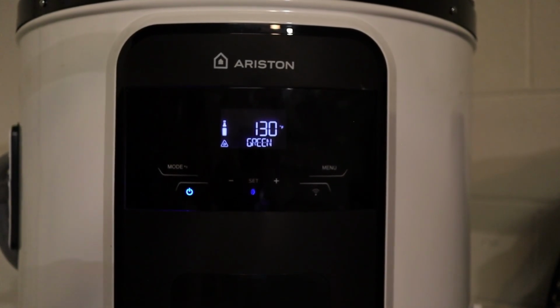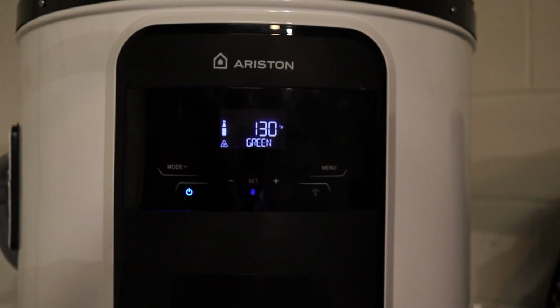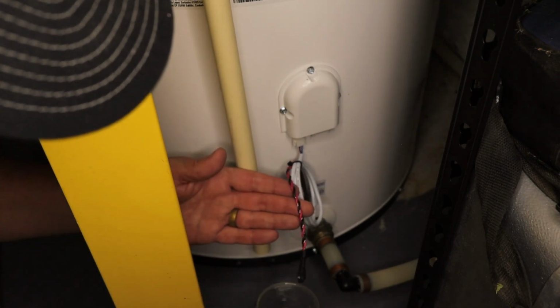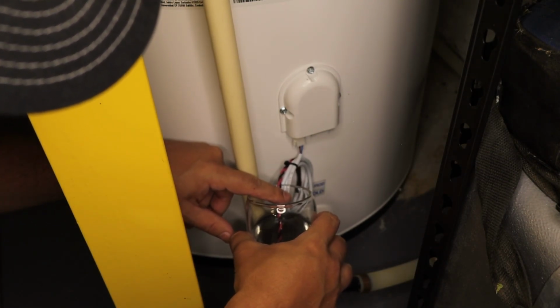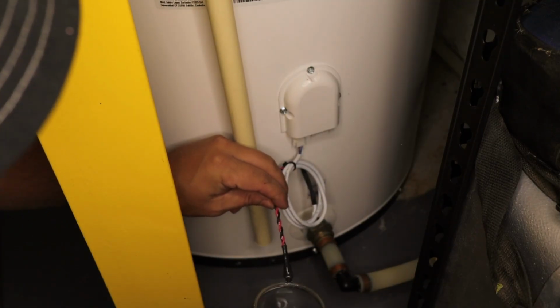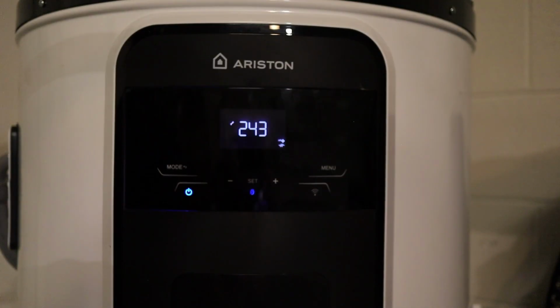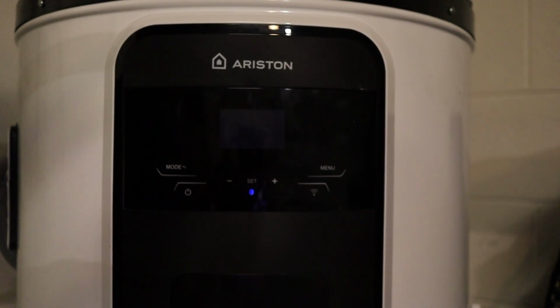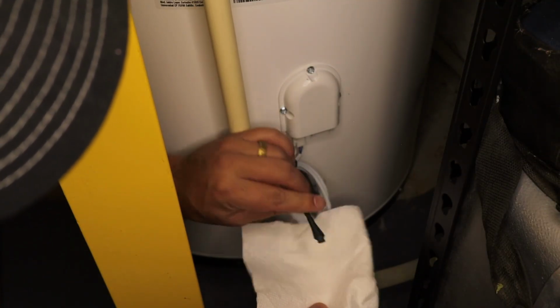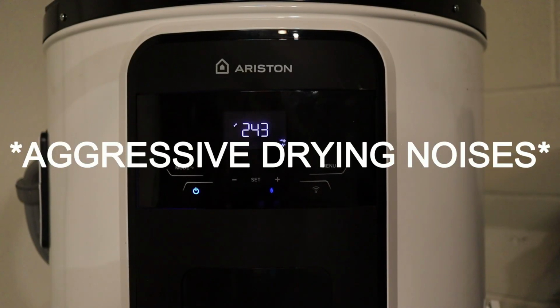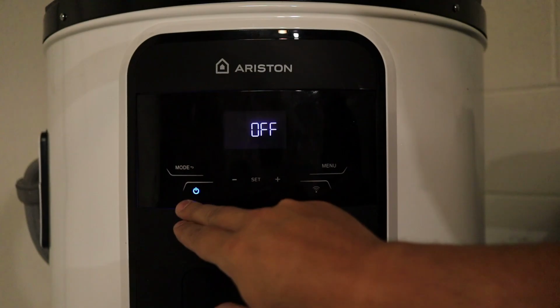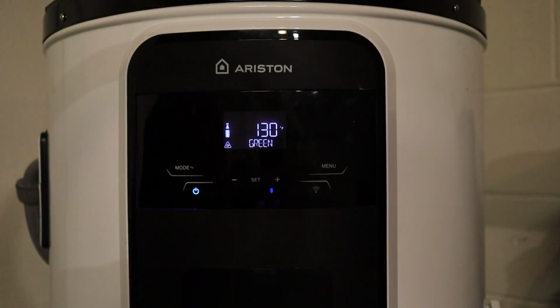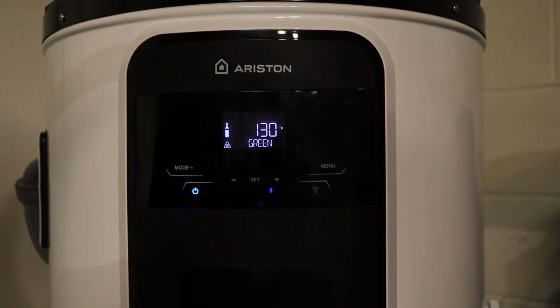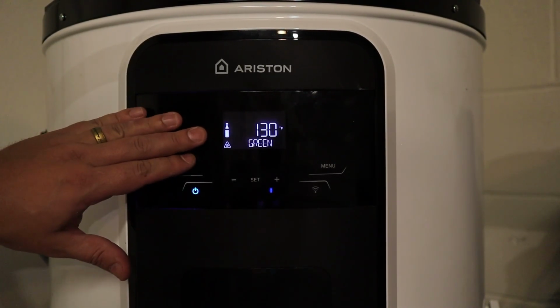So what I'm going to do for you guys live here is actually take this cup of water, and I'm going to take the leak sensor here, and I'm going to go ahead and dip this leak sensor in a little bit of water. And we should see 243 pop right up. Okay, so as you can see, 243 has popped up on the screen right here. Now all I'm going to do is dry off this sensor, obviously remove it from the water, dry off the sensor, and we're going to see if we can get this error to clear. And there you go. We just reset the unit by tapping twice on the power button, getting that guy back on there. And as we can see, our error has cleared and we are back in heating mode.